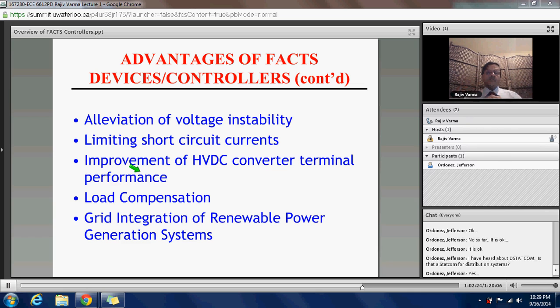Now these inverters require reactive power. And their reactive power consumption can be very high. It can be as high as 60% of the rating of the whole inverter. So this reactive power is taken from the grid. And if the grid is weak, then it cannot supply the reactive power, because of which the voltage fluctuates at the terminals of the inverter. And when the voltage fluctuates, then the inverter sometimes stops working; it maloperates. So you need to do something to regulate the voltage at the inverter terminal. And that is done by FACTS devices. One of the methods of regulating the voltage is FACTS devices.